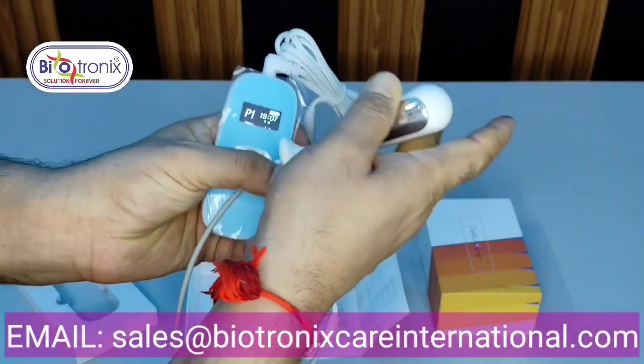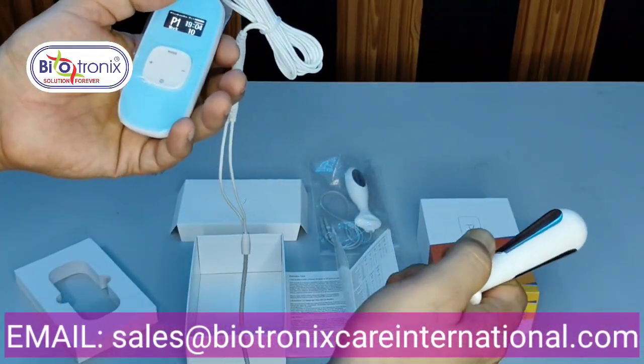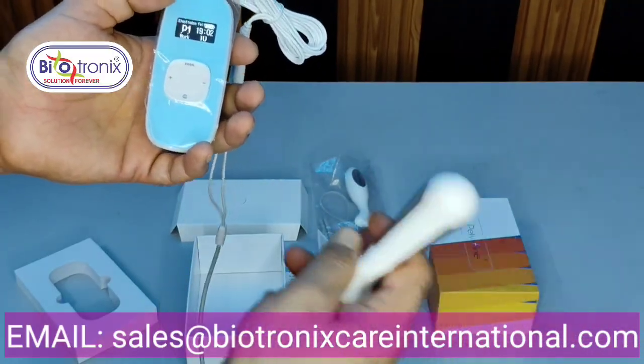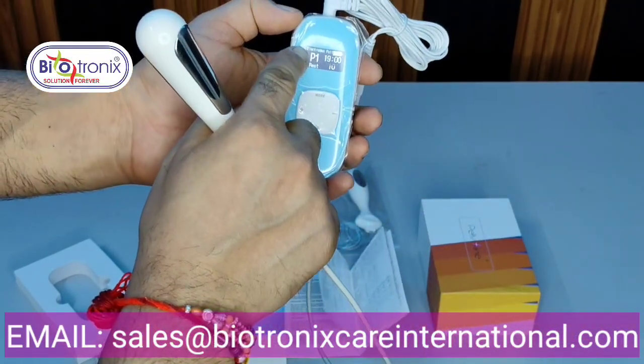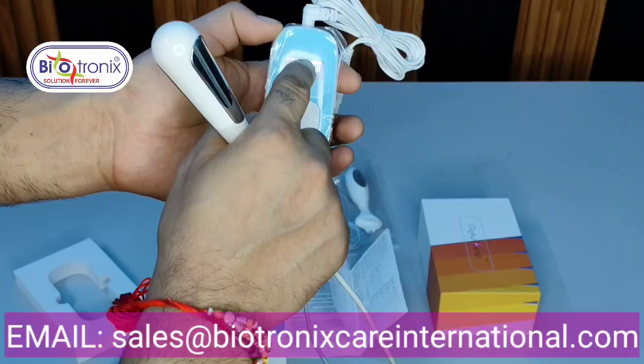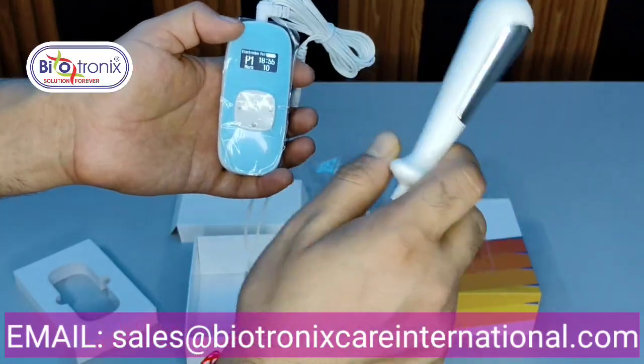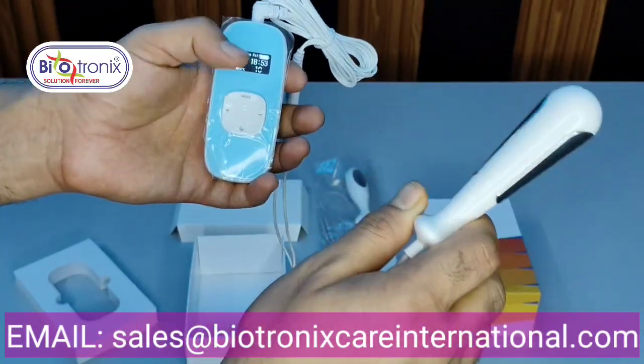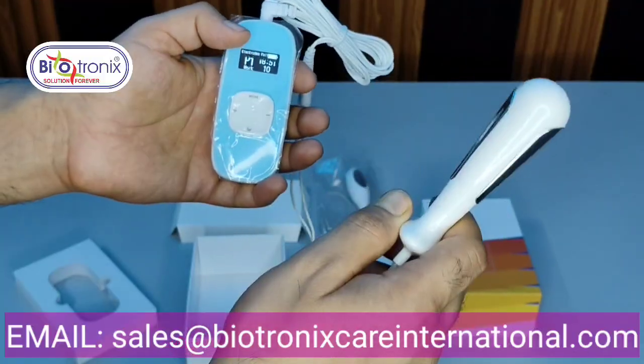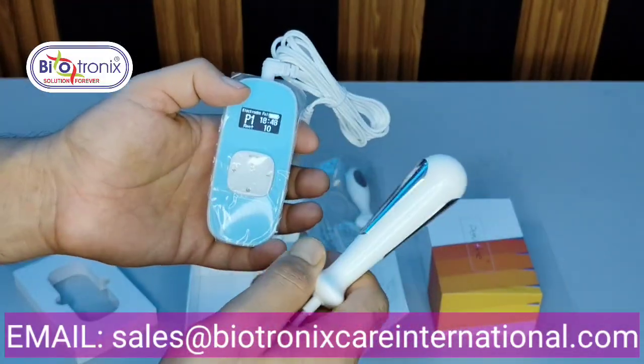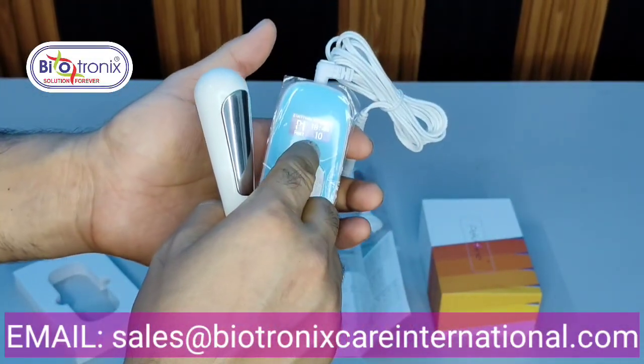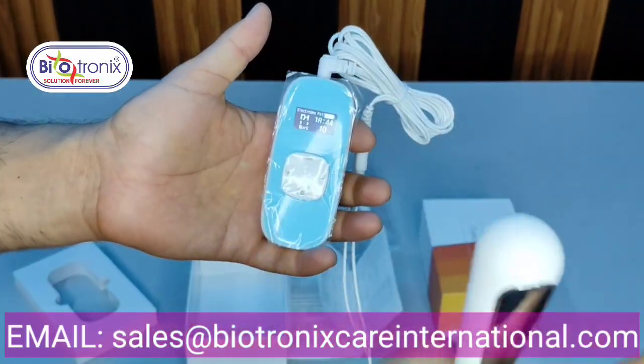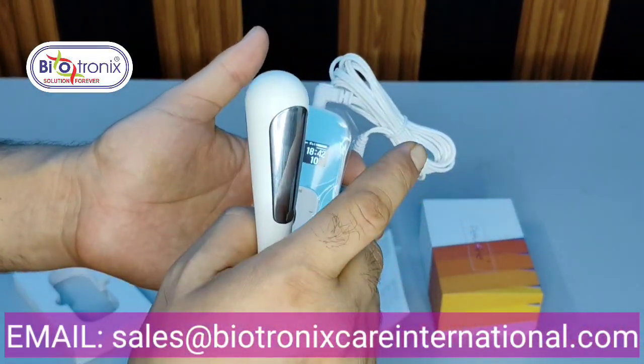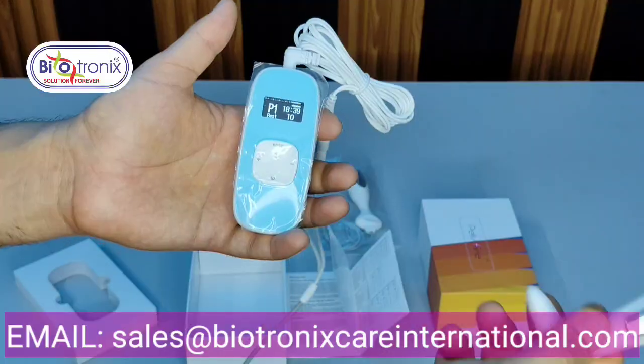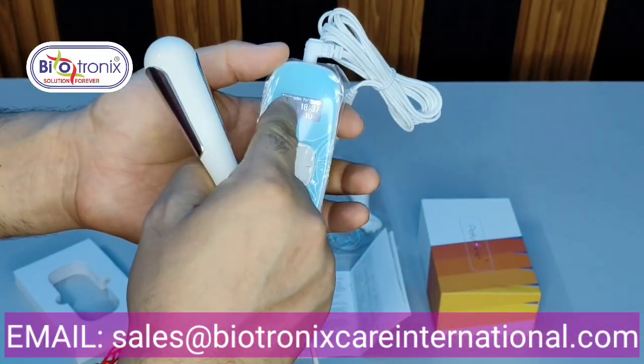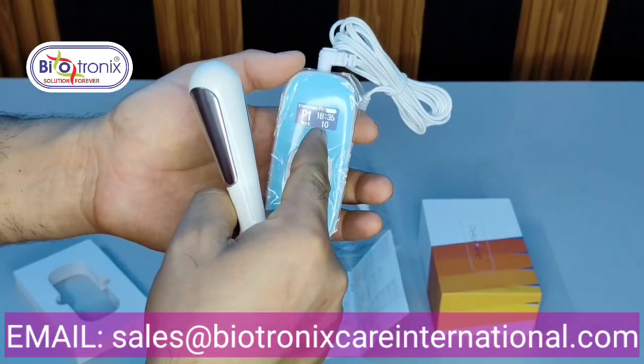When I take the probe out, or when the probe is not in contact with the body, you will find a change over here: electrode fall. It indicates that the electrode is not in contact with the body. So you have to put it back in contact with the body and then use it. By default it will go to intensity 10. It was previously 16-17, but as I release it, it will show me electrode fall, and it will go to intensity 10.